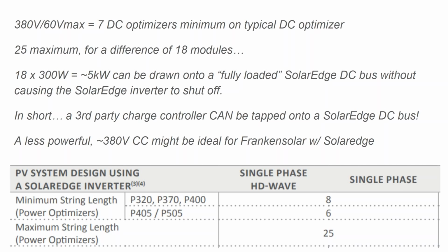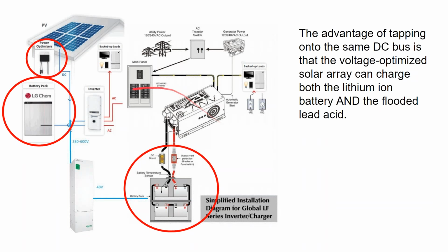This is overcomplicating it, you could have just two separate solar arrays, or just do AC coupled. But what I call Franken solar is a way that you can get double redundancy. If this inverter fails, you still have that inverter; if this battery fails, you still have that battery. So you get double redundancy without repeating any parts, without double stacking inverters. You've got the grid tie functionality, but also the transfer switch.